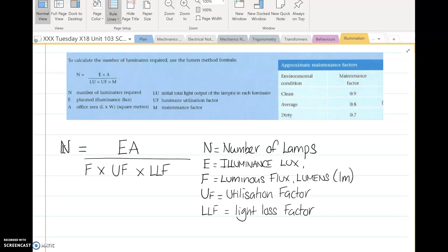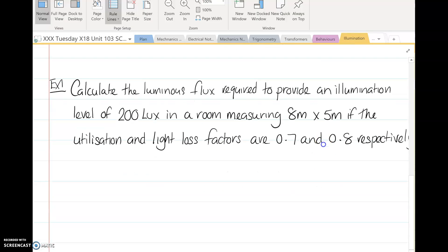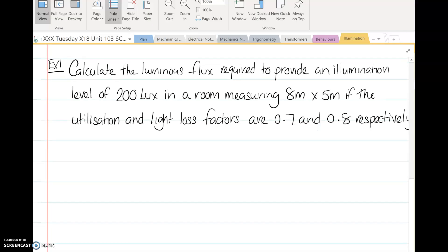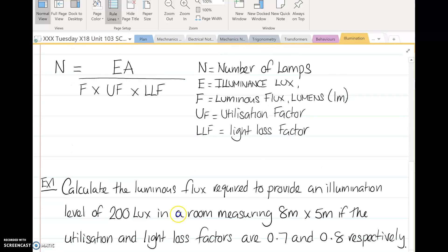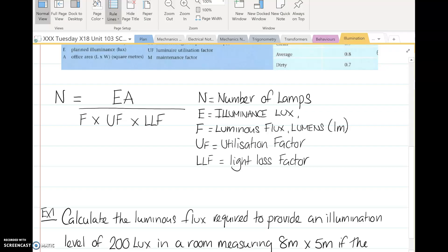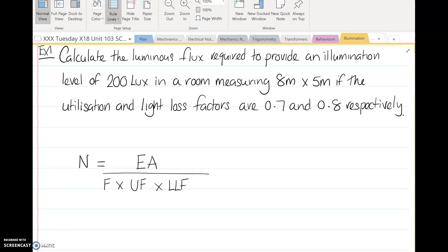So let's look at an example. We're going to calculate luminous flux required to illuminate a level of 200 lux on the surface in a room measuring 8 metres by 5 metres. First thing we need to do is get this formula here, and then we need to rearrange the formula. N is the number of lights, E is the illuminance, A is the area, F is the light output in lumens, that's the utilisation factor, and that is the light loss factor, also known as the maintenance factor.